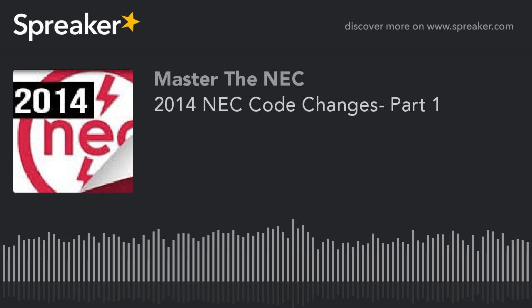So if you go in your code and look for 110.25, you'll see it's all grayed out in the 2014 edition, and it says lockable disconnecting means. Here's what the verbiage says: where a disconnecting means is required to be locked open elsewhere in this code, there are places in 422 and 430 that might have a requirement that the disconnect has to be lockable in the open position.